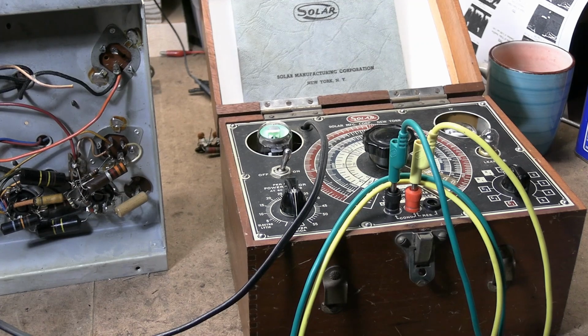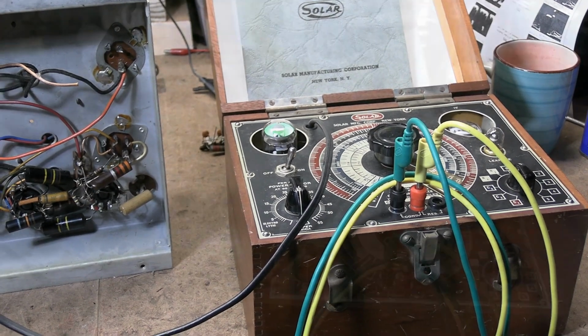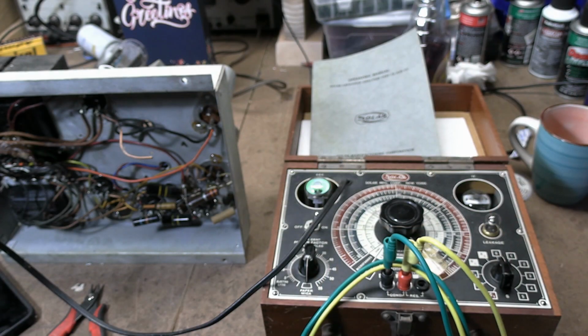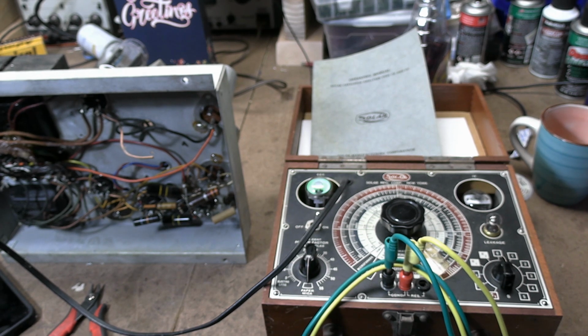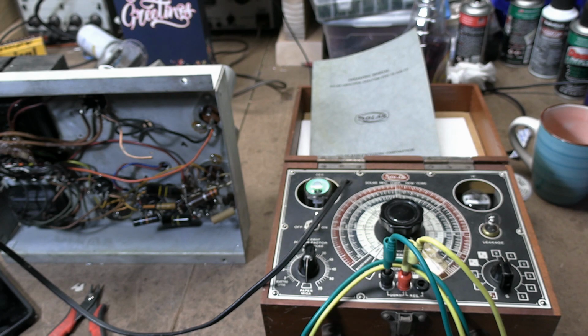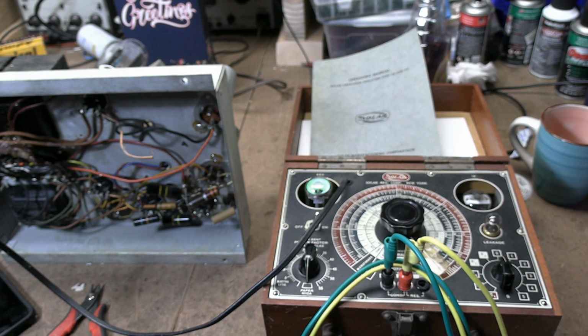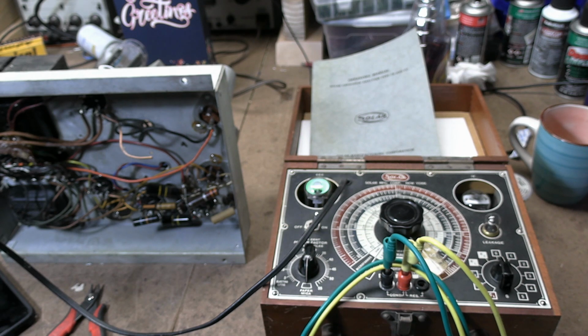There are a number of ways and instruments you can use to test a cap. You may have a modern digital multimeter with a capacitance mode or an ESR tester. You can use those to check capacitance, but I'm of the opinion that to really accurately check these old school high voltage electrolytics for health, you need to test them at full rated voltage and check the leakage current.